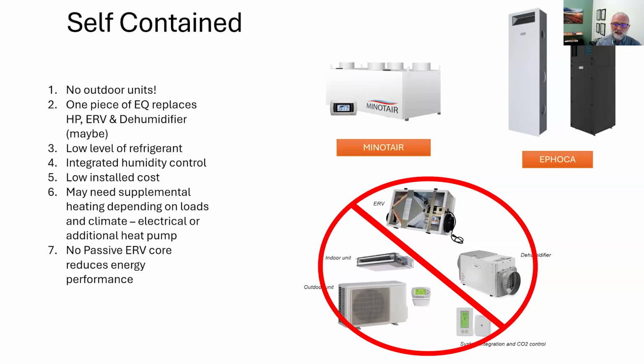There are several manufacturers bringing these products to the US and Canada. Some that are currently available are Minotair and Ephoca. The Minotair unit's a compressor-based device that does heating, cooling, ventilation, and dehumidification. And Ephoca has a vertical all-in-one heat pump that heats, cools, and ventilates through an integrated energy recovery ventilator. These systems offer some unique advantages in multifamily construction. They combine all of these features in one device, potentially saving install and maintenance costs. Both of the pieces of equipment are self-contained, so no outdoor equipment is necessary, which can free up roof space for occupancy or solar panels. Condenser air is ducted from the outside and exhausted back out.